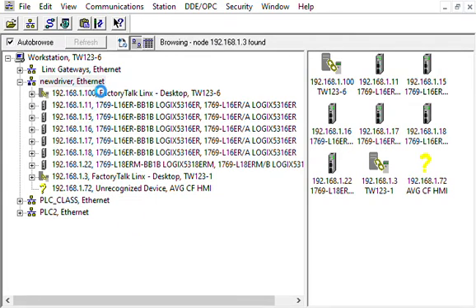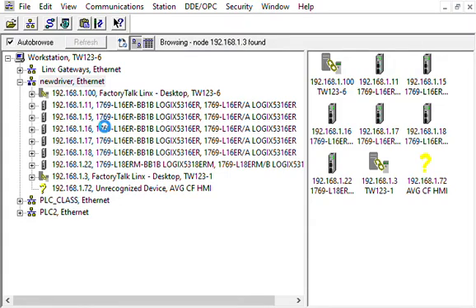Let's see if it'll come back before I shut down the video. So anyway, the data monitor, what's nice about that is you can look at information inside the controller without actually connecting to the controller through the software design program, Studio 5000. And so it's handy. You don't have to interfere with the operation of the controller. You don't have to go online with it. You can just look at it, kind of peek inside and see what it's doing.